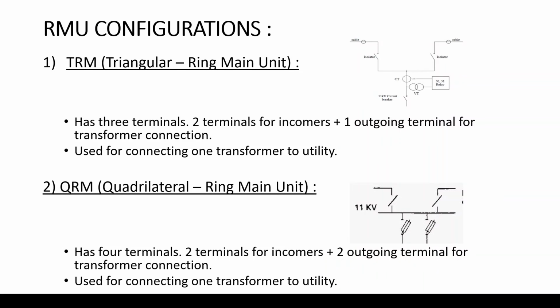First of all, I just want to give a brief, very high level explanation about the RMU configurations. In what configuration are the RMUs available? So basically, in a very basic and straightforward way, you have two configurations, the TRM and the QRM. A TRM RMU is, as you see here in the schematic or a small sketch, single line diagram, basically a triangular ring main unit, which means that it has 3 terminals, 2 terminals for the incomers and 1 outgoing terminal for transformer connection. Therefore, it's used for connecting 1 transformer only to utility. So if I have a project where I have 1 transformer, I would use TRM.